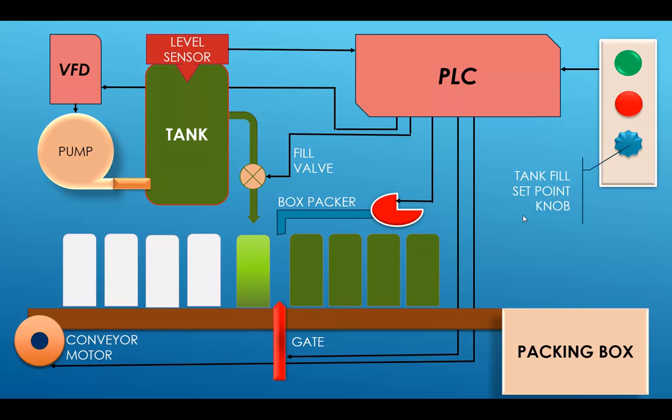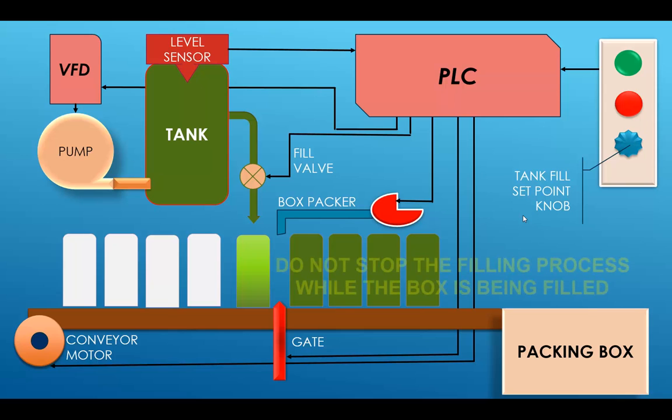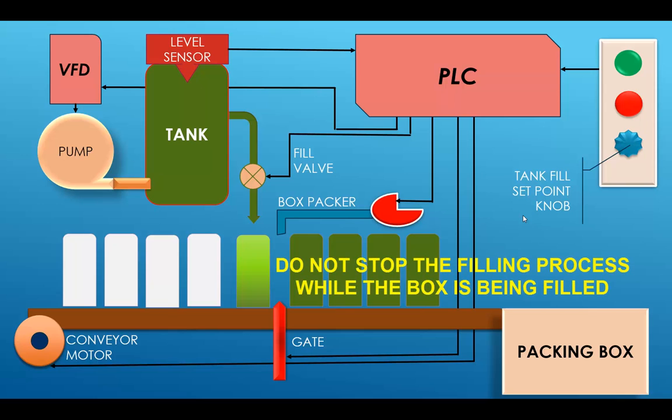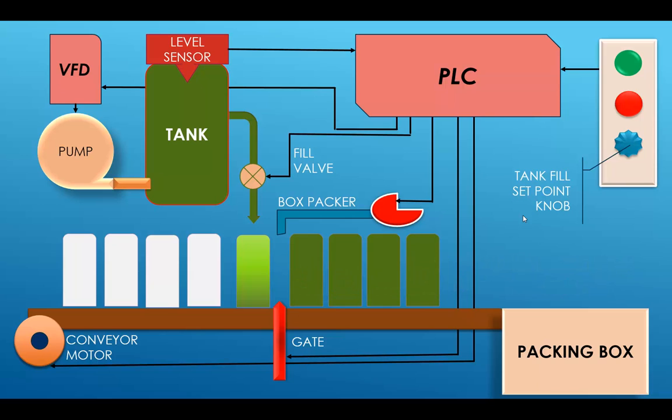To start the process you will energize the system, start the conveyor up and then you will start filling the bottles. You have got your fill time, you have got your gate time and that process runs constantly. Separate from that is your tank filling. The process will look at the level sensor and control the speed of the variable frequency drive, actually control the speed of the pump by varying the inputs to the variable frequency drive.